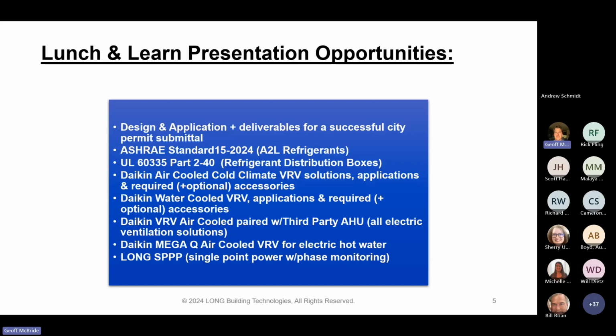So if you're interested in any of these subjects, we've got design and application, plus deliverables for successful city permit submittal. There's a lot of changes that have happened with the new refrigerants, so we can help you with that. The ASHRAE Standard 15 2024 with respect to A2L refrigerants and volume, which coincides with UL 240, which has to do with refrigerant distribution boxes. We'll kind of combine those into one lunch and learn. That's been a very popular one as of late, as you can imagine.